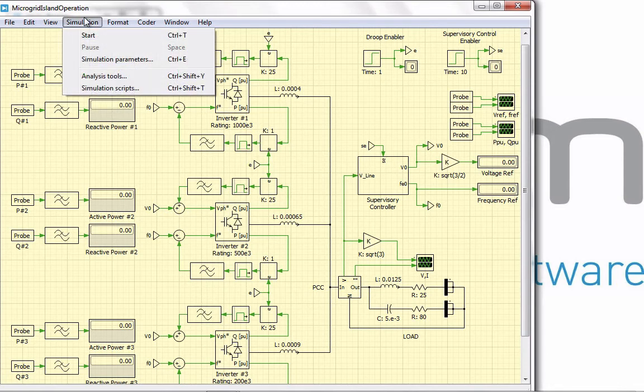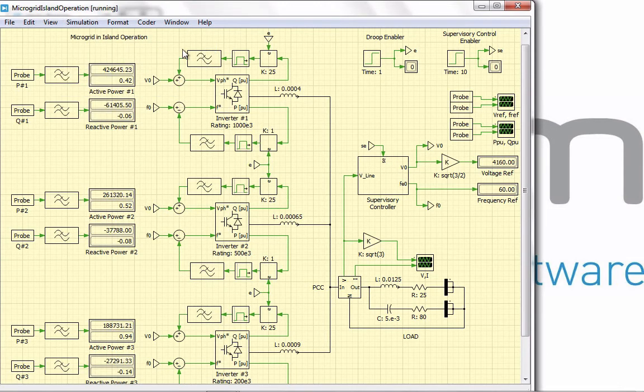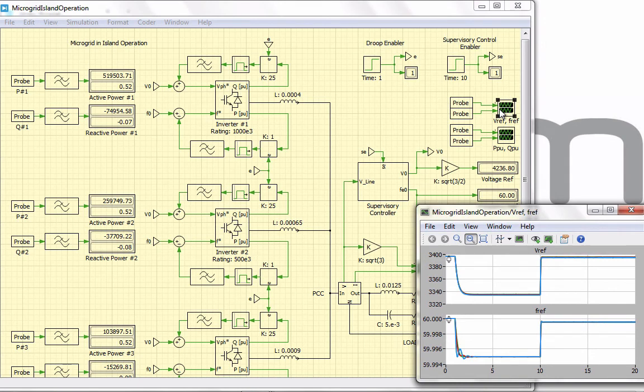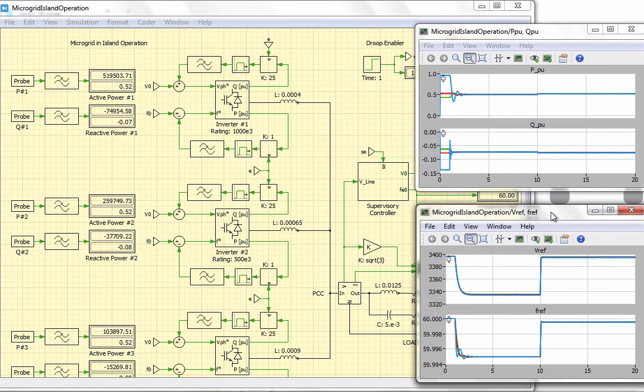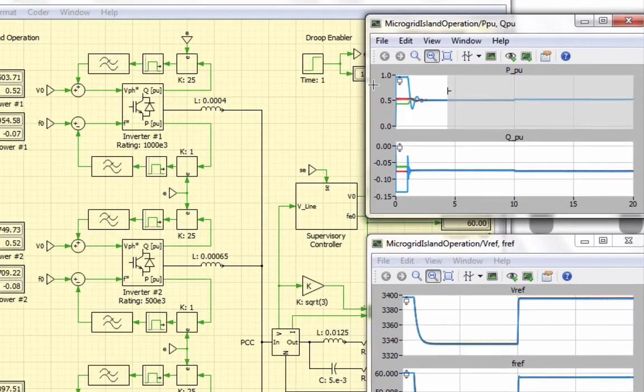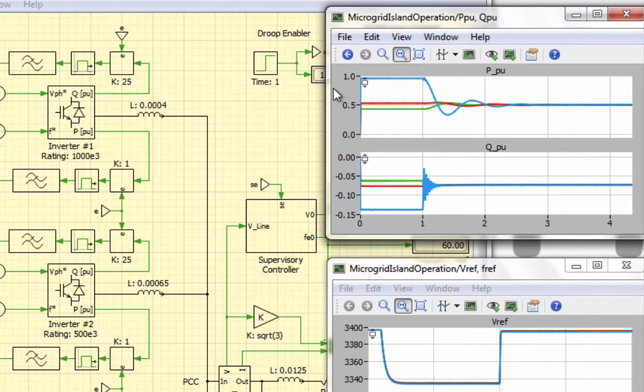Let's start the simulation now. Note that both the droop and supervisory controllers are not enabled at the beginning of the simulation. The droop controller is enabled at 1 second and the supervisory controller is enabled 10 seconds after the simulation starts. Let's observe the reference voltage and frequency waveforms as seen by the droop controller as well as the waveforms of per unit real and reactive powers. The unit with 200 kVA rating is close to overload at the beginning of the simulation when both the controllers are off.